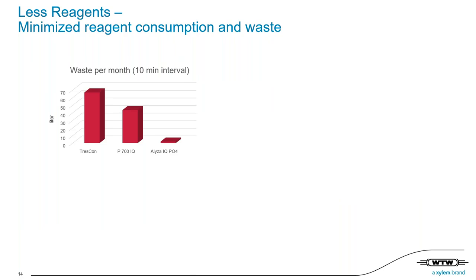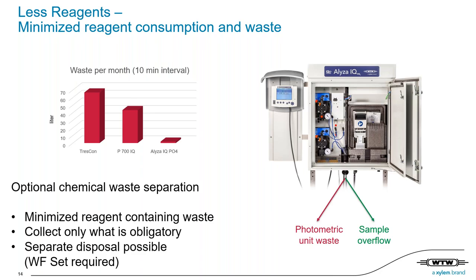Here you see the chemical-containing waste volume of all three analyzer generations. That means the waste after the photometric unit. With Alyza IQ reducing this waste more than 90% compared to the predecessors TresCon and P700, and also to other traditional analyzers available in the market. In addition, traditional wet chemical analyzers don't have the option to separate chemical waste from the overflow, and thus the liquid waste amount is even higher. Fortunately, the Alyza IQ platform offers an optional waste collection system to only collect what is obligatory, resulting in a further operating cost reduction where charge disposal is mandatory. So again, you have the maximum flexibility to just set everything for your application.